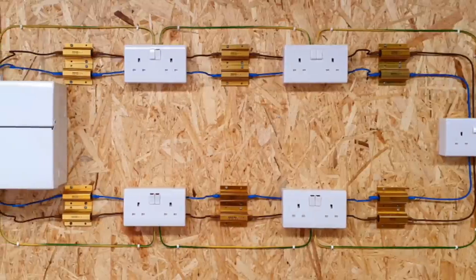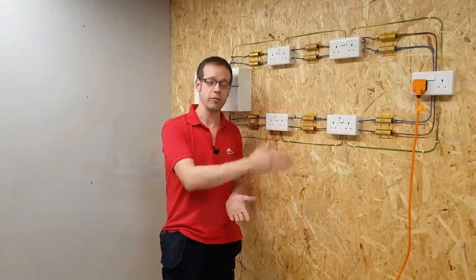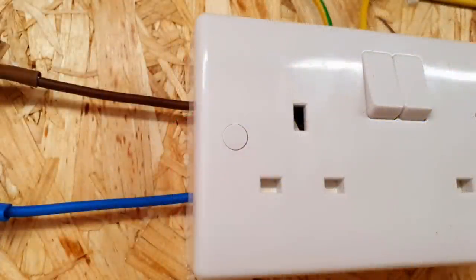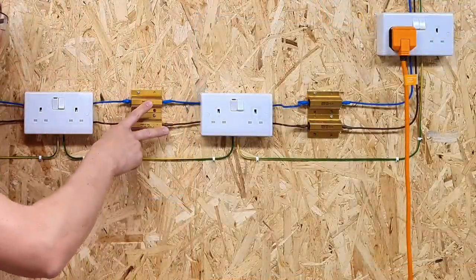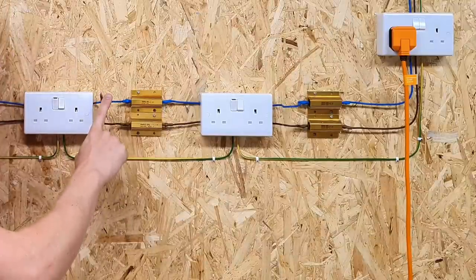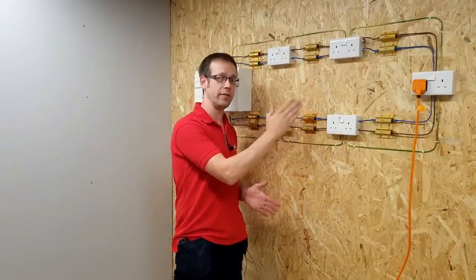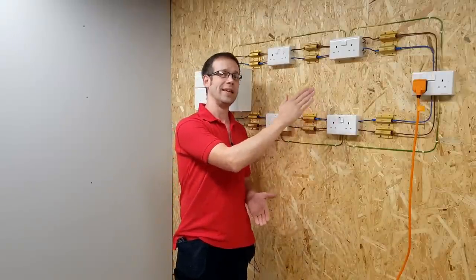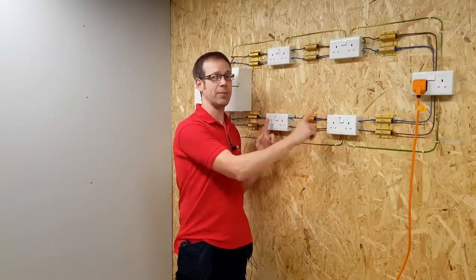I've constructed a ring circuit here using these double sockets and surface-mounted pattresses sent to us by BG — they really were lovely to fit, with plenty of room in the colour-coded terminals in the back and great styling on the front. You'll notice that between each socket there's a couple of power resistors, one connected to the line conductor and one connected to the neutral. These are just here to mimic the resistance in the cable that we'd find in a real-life circuit. Each one is the same value of 0.22 ohms, which means this represents a ring final circuit where each piece of cable is exactly the same length between sockets.